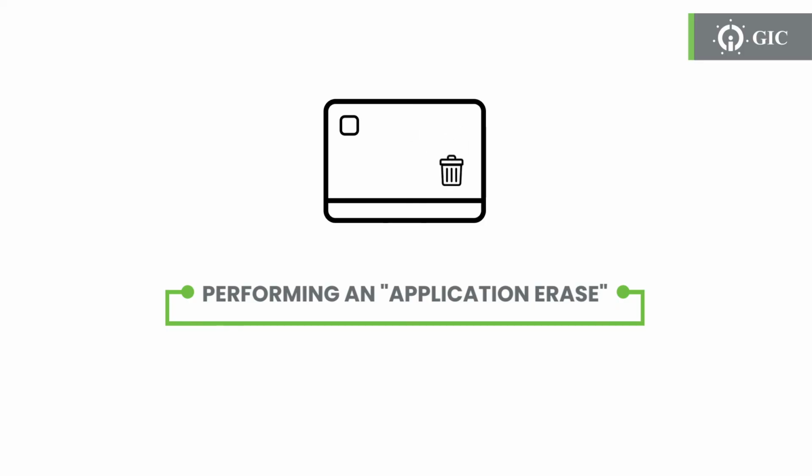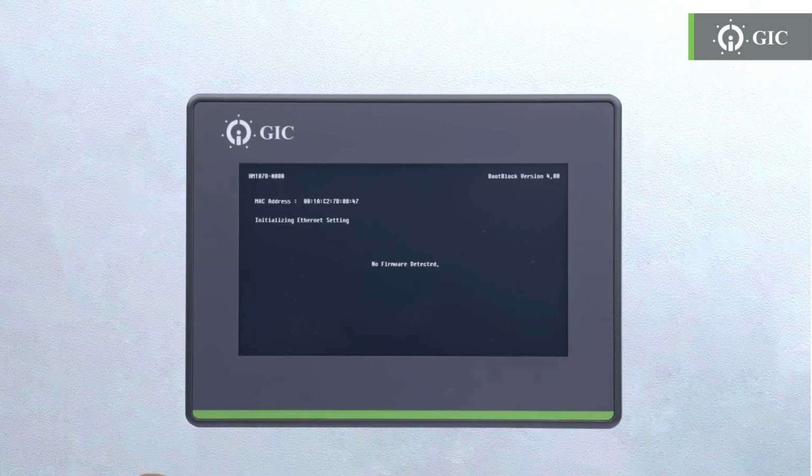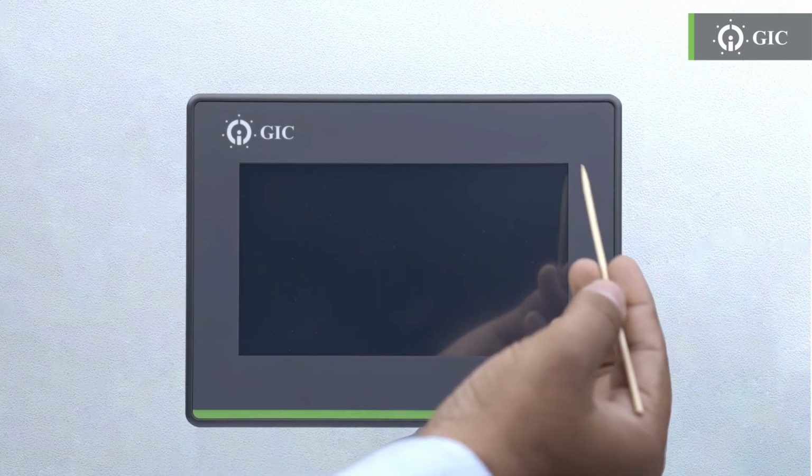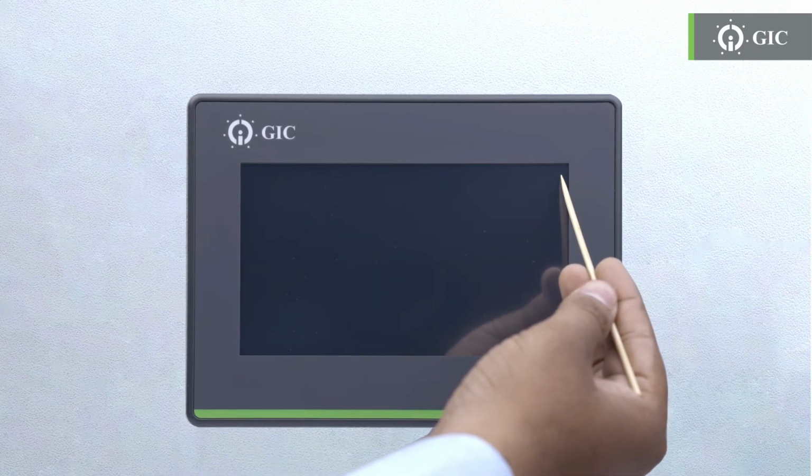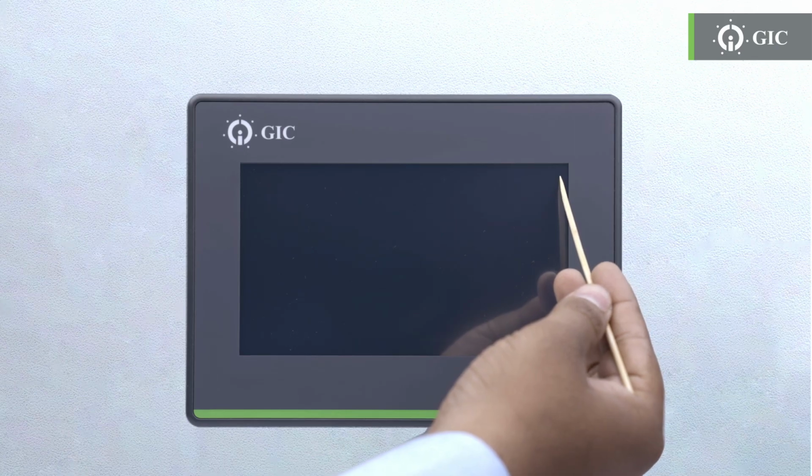Just like you learned how to perform a firmware erase, you can also do an application erase. To begin with, firstly power off the unit. Step 2. Press on the right side top corner. Holding it for 3 seconds, power on the unit. Watch as it enters the application erase mode.